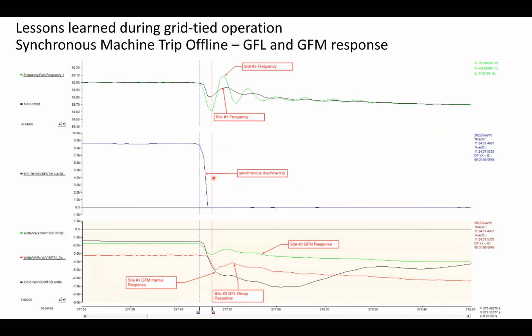This was the same generator here in blue. This was another trip that it had. Luckily, it was only putting out about 8.5 megawatts at the time. On the bottom, we have 3 trends. Site 1 is a grid forming inertial type response, seen in black, and that has virtually 0 delay to frequency dropping. Site 2 is a grid following droop response, and you'll see there's a delay in red in its response. And then site number 3, which is grid forming, did respond with virtually 0 delay.